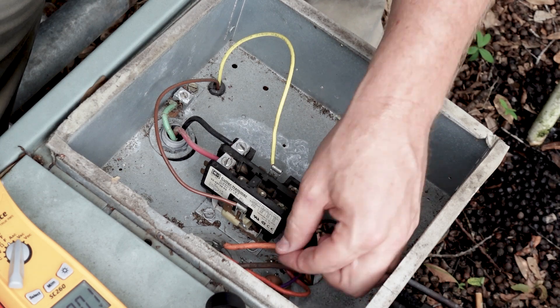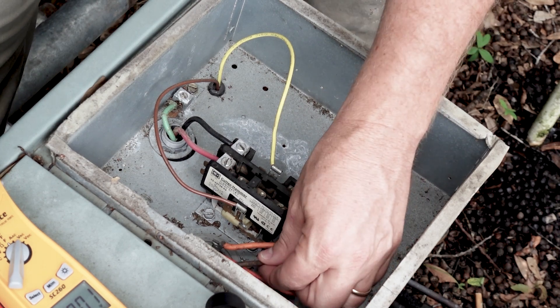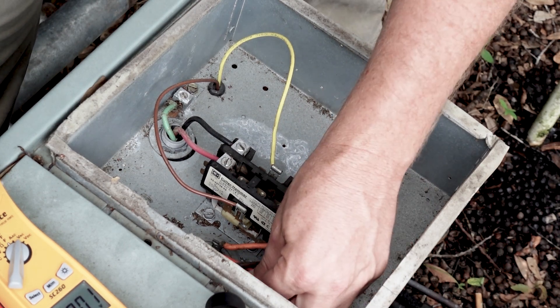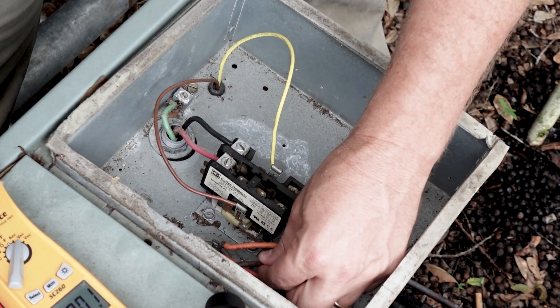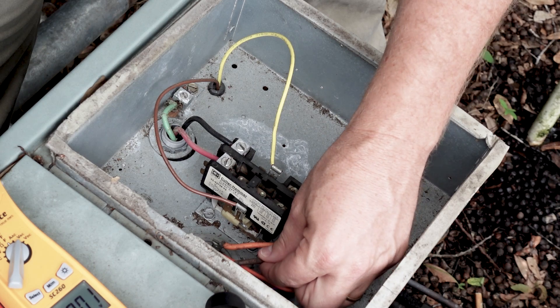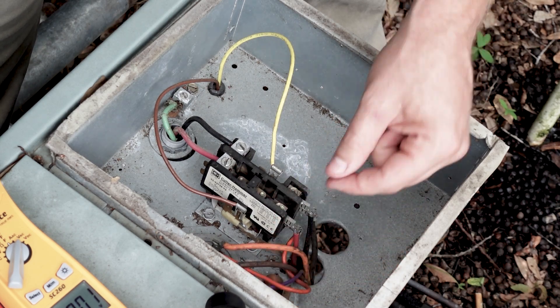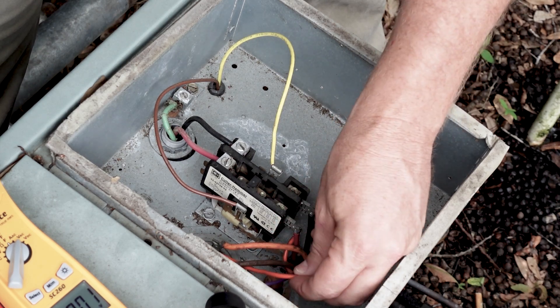If we look at our capacitor, this one is going to be marked fan. This one will be marked Herm. When it's marked fan, that's actually our fan start winding. When it's marked Herm, that's our compressor start winding.